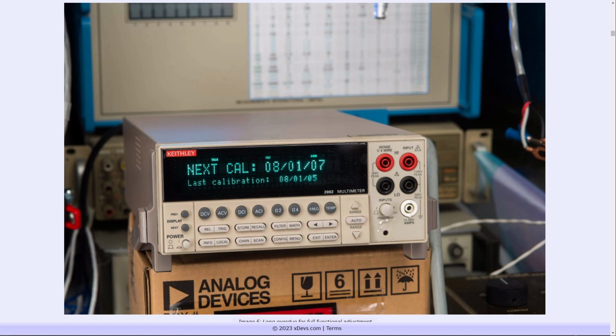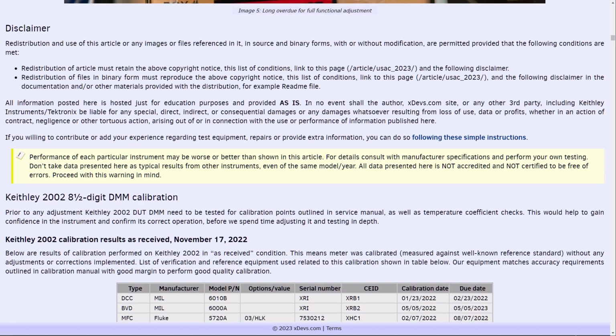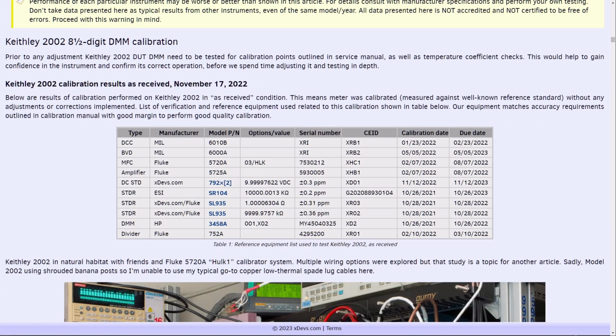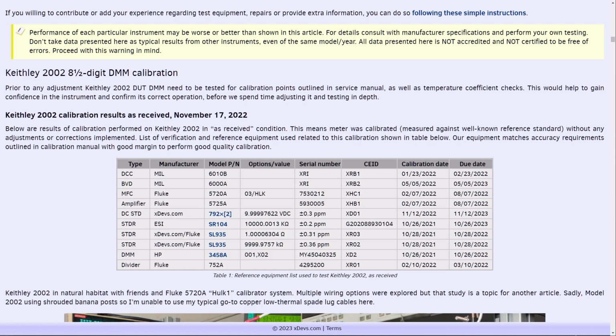Feel free to use data and results from this article or video, but if you do so, don't be evil and give links to the source here at xdevs.com. Table 1 lists the equipment used to perform the as-received condition calibration for the Keithley 2002. The main tool is a Fluke 5720A calibrator, which was tested and calibrated against a reference HP 3458A, resistance standards and resistance bridges from Measurements International. For AC voltage, a Fluke 5725A was used for higher frequency tests.